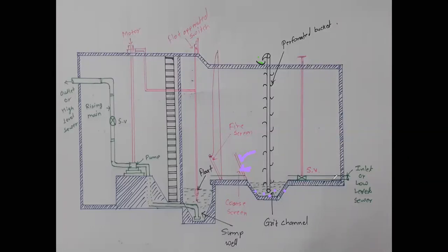One of the problems we discussed is the fluctuation in discharge. The discharge is not constant, so it keeps changing. If the discharge is less, should we change the capacity of the pump, or if discharge suddenly increases, should we increase the capacity of the pump? Is it possible? It is not possible. So we should decide a constant capacity of the pump, and we should make it possible to have a constant flow rate, constant discharge. For that purpose, the sump well has to be designed.